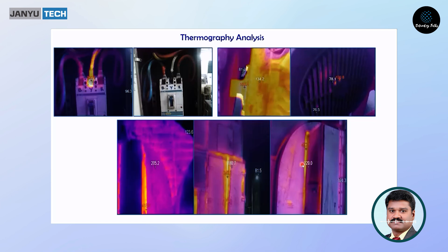There is a small difference between the driving end temperature and the non-driving end temperature. If the difference between the driving end temperature and non-driving end temperature is more than 20 to 30 degrees, then automatically the motor is not capable of dissipating the heat to the outside, so the motor starts boiling. See also the pulley side, the contact side, the back side of the machine, other machines, and similarly contactors, the body of the motor, so many things.